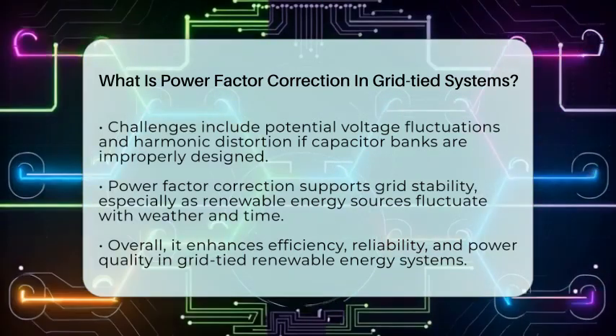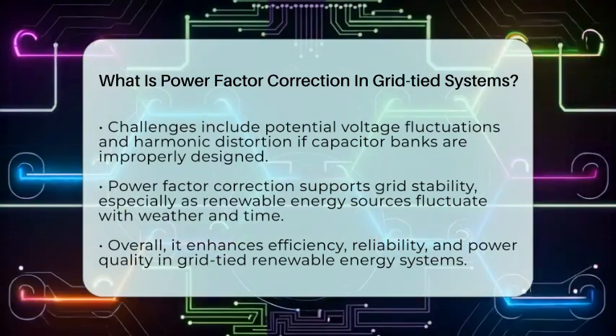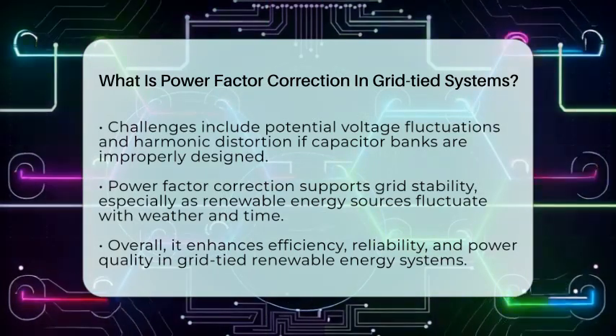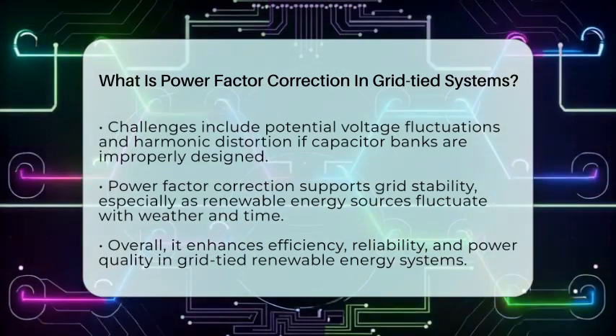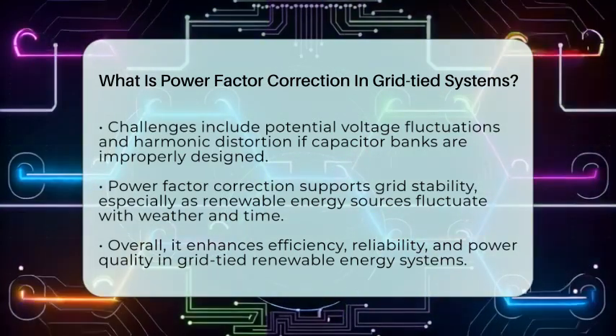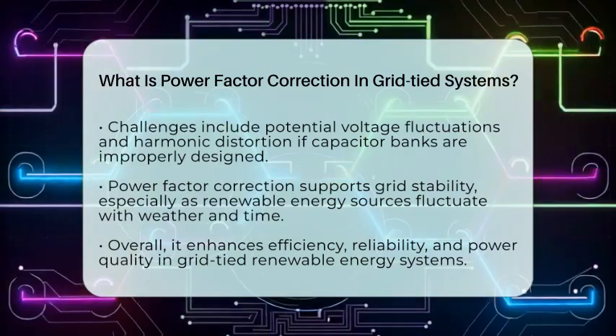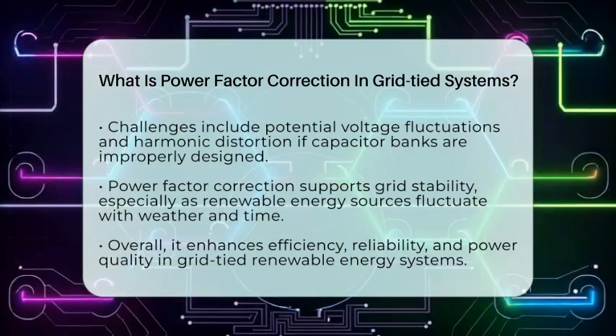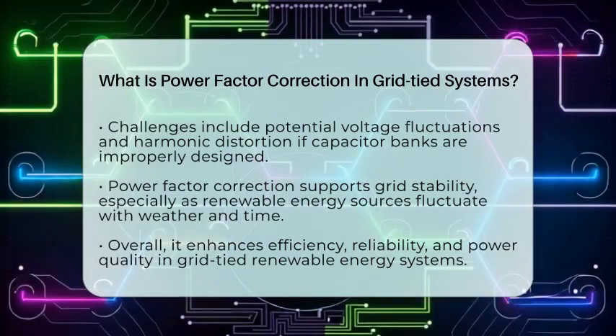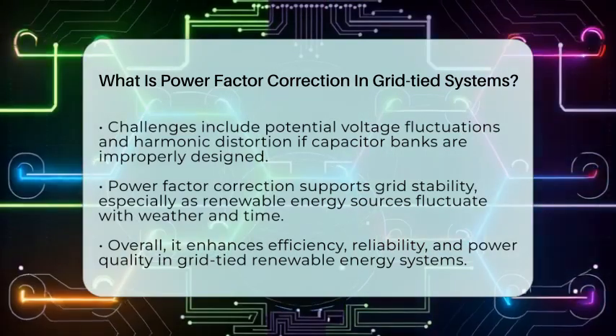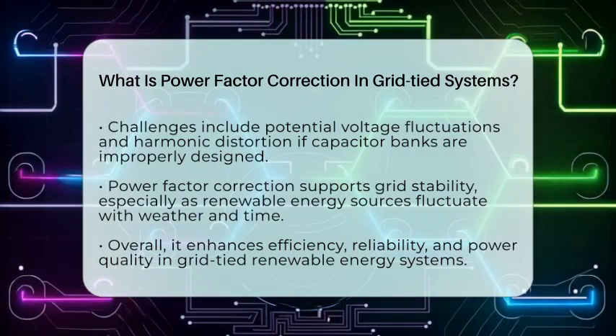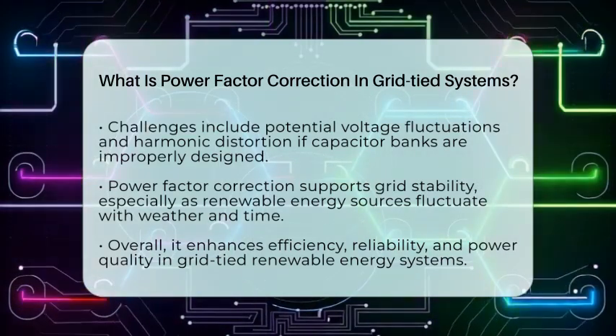Improperly designed capacitor banks can cause voltage fluctuations or harmonic distortion. Reactive power compensation needs to be carefully controlled because renewable energy generation can fluctuate with weather conditions and time of day.